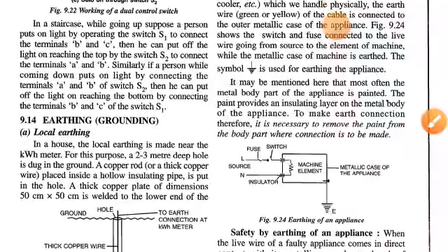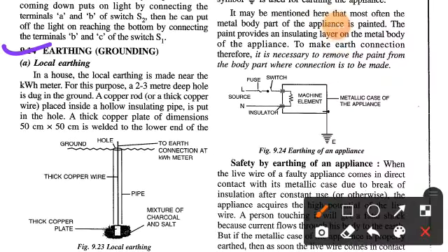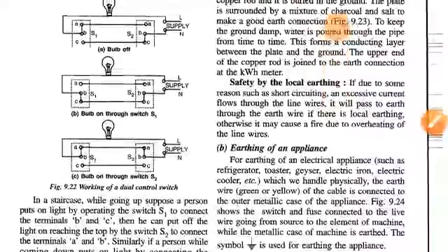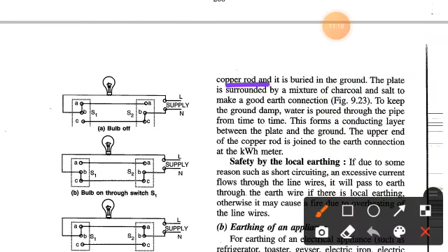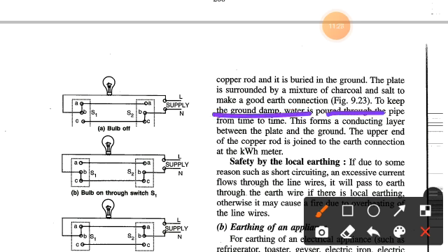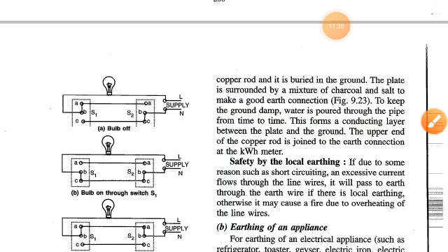Regarding earthing: local earthing in a house is made near the kilowatt-hour meter. For this purpose, a two to three meter deep hole is dug in the ground, and a copper rod or a thick copper wire placed inside a hollow insulating pipe is put in the hole. A thick copper plate is welded to the lower end of the copper rod and buried in the ground. The plate is surrounded by a mixture of charcoal and salt to make a good earth connection. To keep the ground damp, water is poured through the pipe from time to time, forming a conducting layer between the plate and the ground. The upper end of the copper rod is joined to the earth connection at the kilowatt-hour meter.